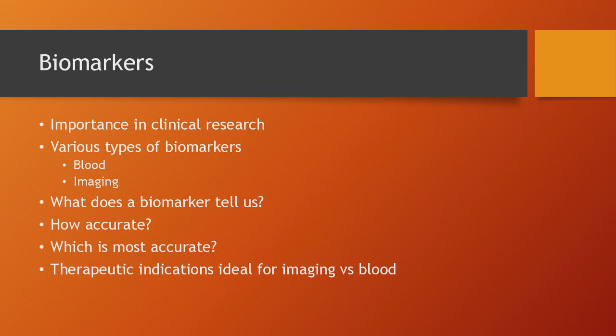And we simply decided to work with the same requirements that are established right now for blood laboratories, for biological sample laboratories, and we decided to work with the European Medicines Agency regulation that establishes that for any bioanalytical test, the variability should be below 15%, and the accuracy compared to the ground truth should be also below 15% of relative error.